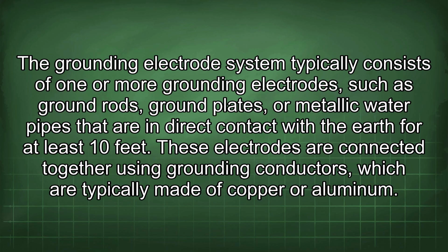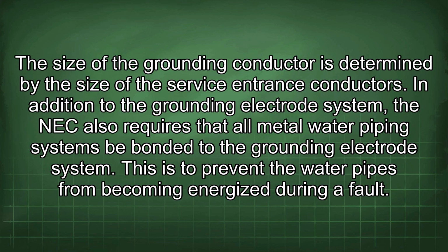The grounding electrode system typically consists of one or more grounding electrodes, such as ground rods, ground plates, or metallic water pipes that are in direct contact with the earth for at least 10 feet. These electrodes are connected together using grounding conductors, which are typically made of copper or aluminum. The size of the grounding conductor is determined by the size of the service entrance conductors.